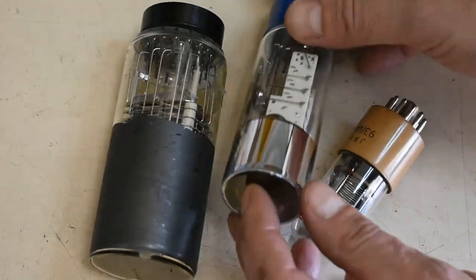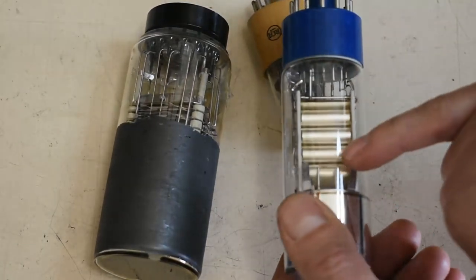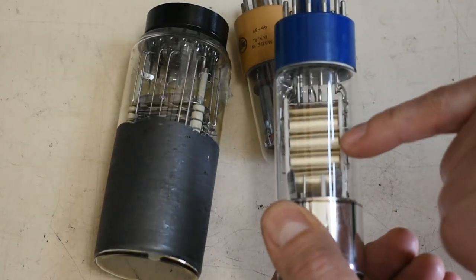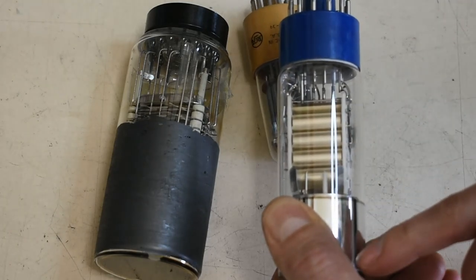You have a photocathode, in this case it's coated onto this glass front, and you have dynodes which are electrodes at different potentials that cause a cascade of electrons that come from the photocathode to the anode for detection.